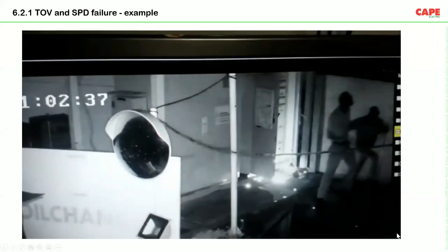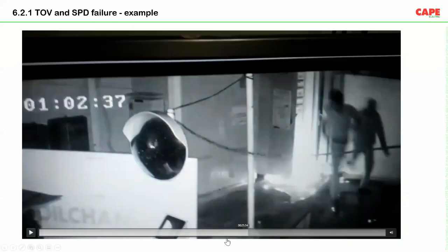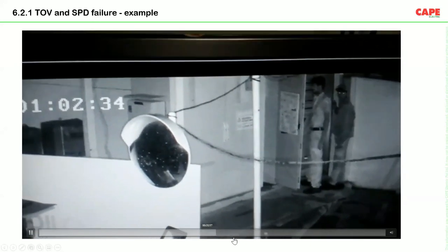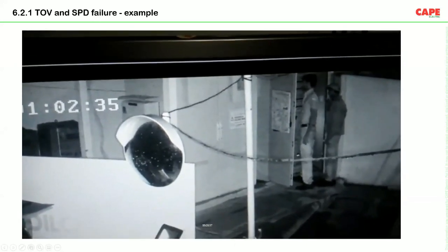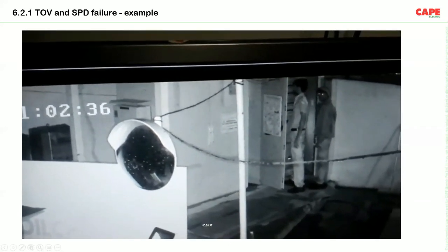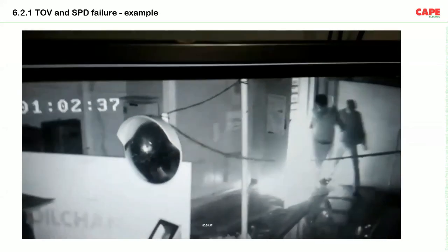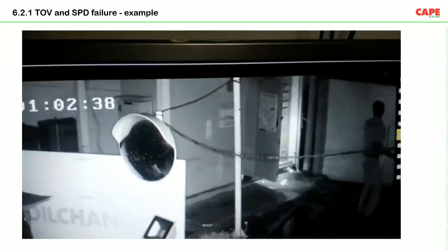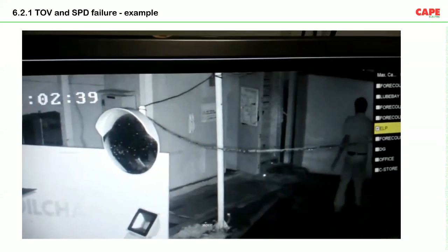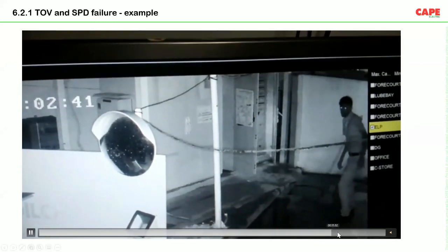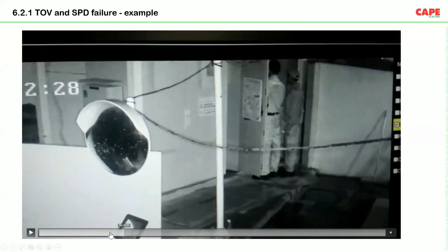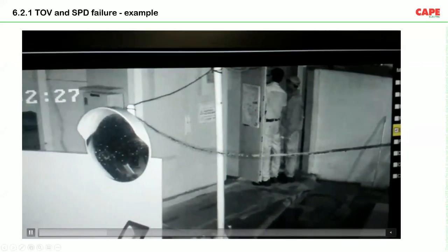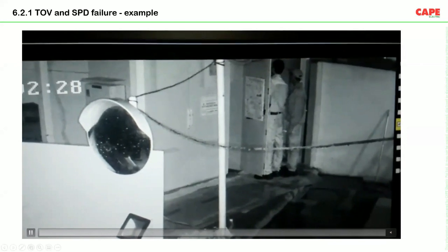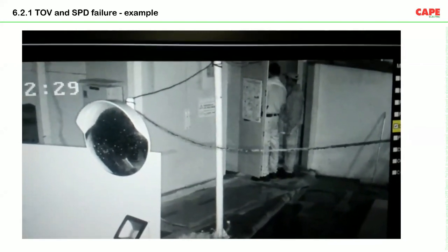You see what happened? So basically, they are checking the panel board, and suddenly there is an explosion. This explosion is because of an SPD. Now let me switch off the volume. Okay.